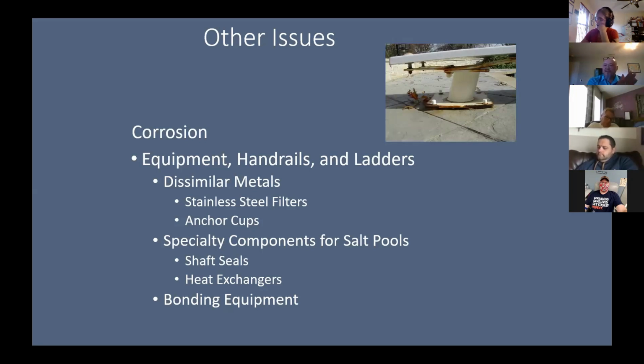Fortunately, in our industry there's been a whole series of specialty components for salt pools. Shaft seals are designed for salt pools. Gas heaters are now coming out with a salt pool heat exchanger. Titanium heat exchangers are pretty much impervious to any kind of chemical attack, so with heat pumps, you don't have to worry, they're all titanium heat exchangers. But with your other equipment, if there's a salt option, that's a good thing to do.